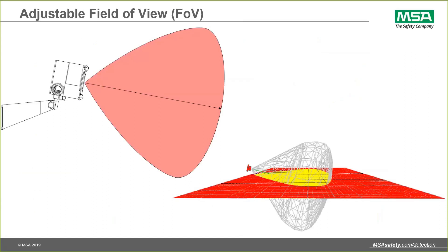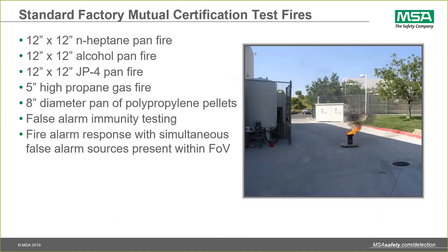It's important from an end-user perspective to be confident that the flame detector you're installing is capable of seeing the fire you expect. Factory Mutual provides certification on performance to different fire types — including heptane, alcohol, JP4 kerosene-based jet fuel, propane, methane, propylene, and Class A solid material fires. They also perform false alarm immunity testing and fire alarm response testing with false alarms simultaneously present in the field of view, to ensure the detector delivers the performance claimed by the manufacturer.